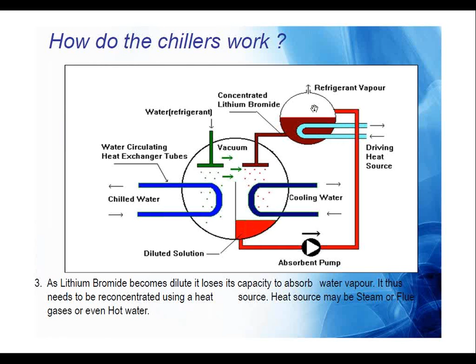So the boiling will be in such a way that only refrigerant will get evaporated from this section, and the lithium bromide will once again be brought back to its original concentration of 64%. So that the same concentrated lithium bromide we can once again use in the absorber section, and the cycle will be a closed circuit for lithium bromide. Whereas the refrigerant which is evaporated from this section will go to the condenser side.